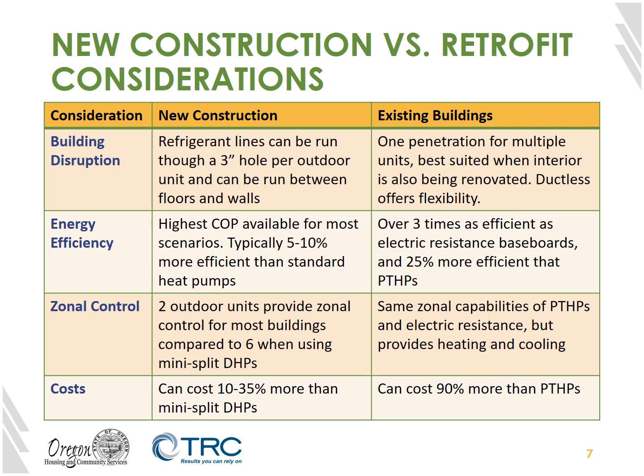So that's space required, that's penetrations through the building, and if you used 6 multi-split systems, each of the units that are connected, you would only be able to heat all at the same time or cool all at the same time per outdoor unit. Whereas with a VRF system, again, you have that flexibility for zonal control. When we compare this to existing buildings, again, you can have zonal control with package terminal heat pumps. You can have zonal control with electric resistance heat. You're simply not going to get that heating and cooling potentially simultaneously.